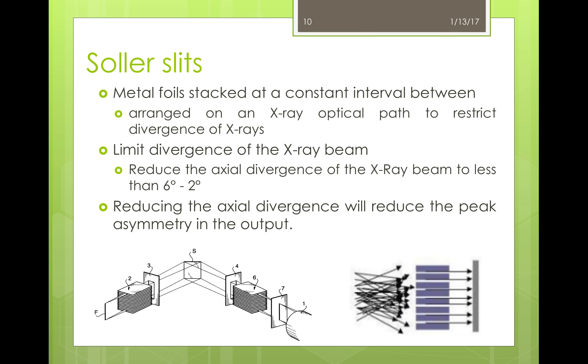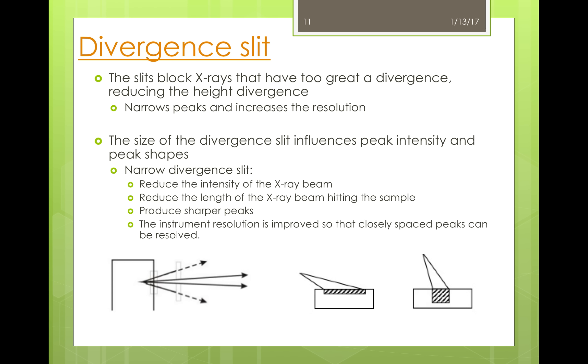Let's take a closer look at the Soller slits. These slits are metal foils that are stacked in parallel with constant spacing. The job of the slit is to reduce the angular divergence of the X-ray beam and to keep it on the correct path. By doing this, the peak asymmetry of the signal will be greatly reduced, so you'll get better data. The divergent slit is used to block X-rays that have too great of a divergence. By reducing the spread of the beam, known as the height divergence, the resolution of the output is significantly increased. The divergent slit comes in a variety of sizes, which affect the peak intensity and the shape of the output. For example, a narrow divergent slit will reduce the intensity of the beam and the length of the X-ray beam, produce sharper peaks, and allow for greater resolution than a wider divergent slit would.